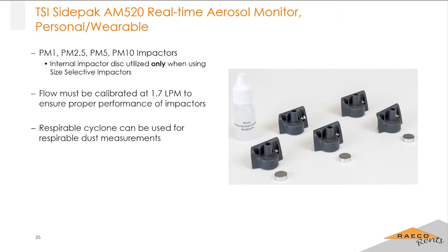Here's a picture of those impactors. You can see the plastic piece that gets screwed onto the SidePak and where you would connect tubing. Then there are the small impactor discs that go inside. You just put a little drop of oil on those, install them on the SidePak, and you're ready to go. Important to note too, if you're not using a size selective impactor, then you should not be using that impactor disc. If you're just measuring total dust, you put a blank impactor on, and there's not going to be one of those discs behind it. Again, the 1.7 liters per minute ensures that those impactors or the cyclone are working properly.